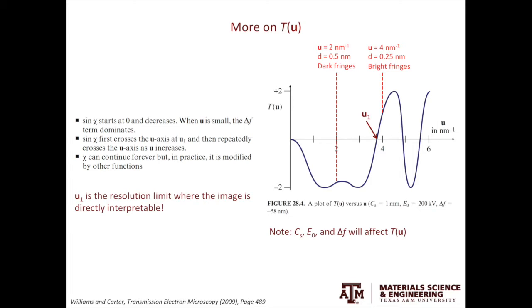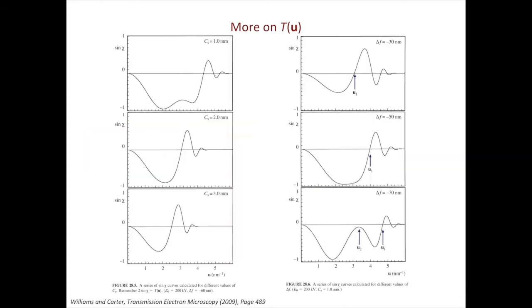If you read the legend of the figure, it specified the spherical aberration coefficient, the acceleration voltage of the TEM and the defocus value. We cannot easily change the acceleration voltage of the TEM. So next, we'll look at the effect of the spherical aberration coefficient and the defocus value on T(u). The figure on the left shows the effect of Cs, the aberration coefficient, on T(u). As Cs increases, the first crossover, u1 decreases. That tells us as Cs increases, there is a degradation of the resolution for the microscope.